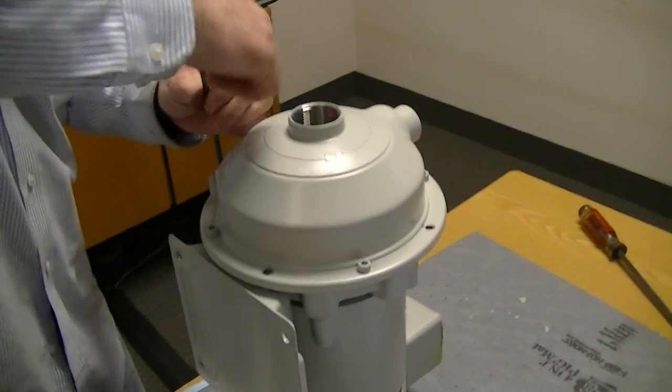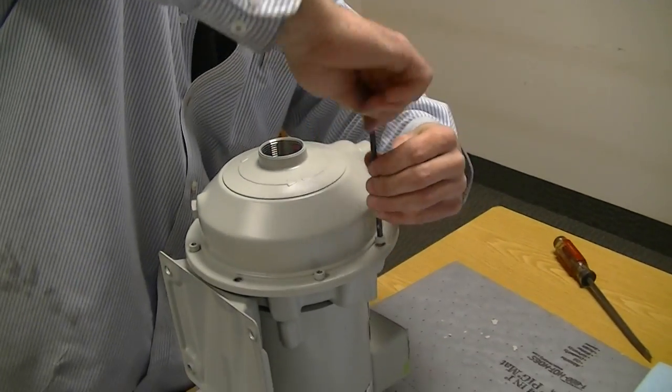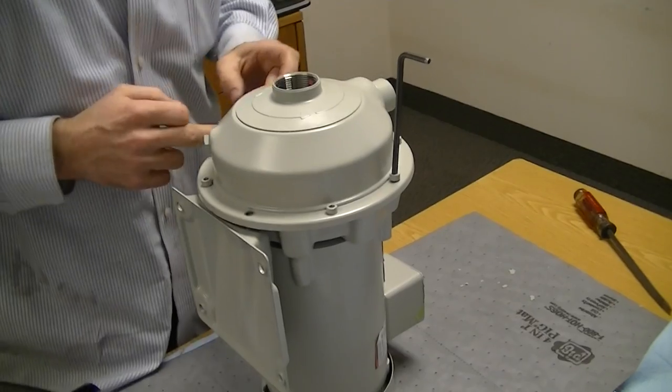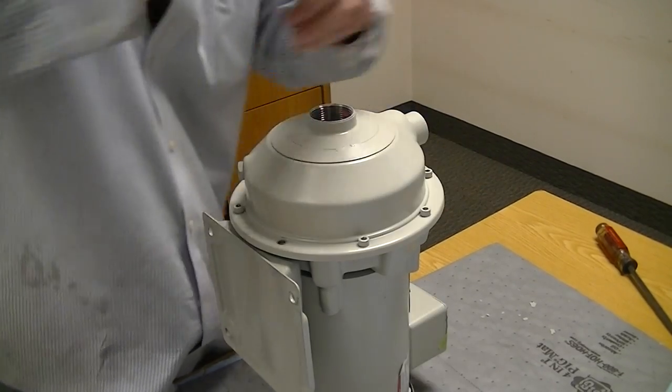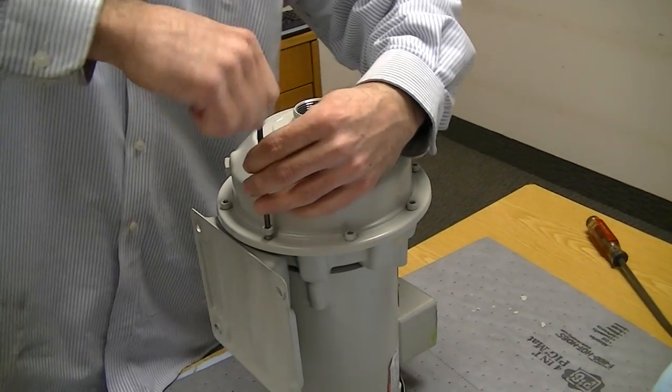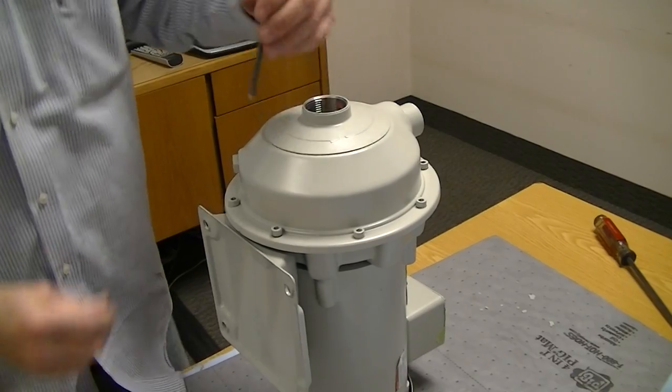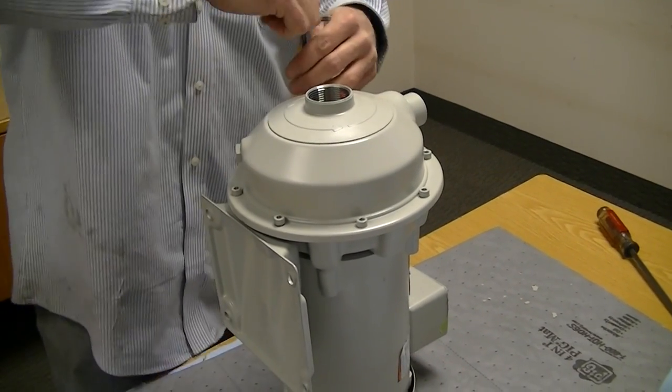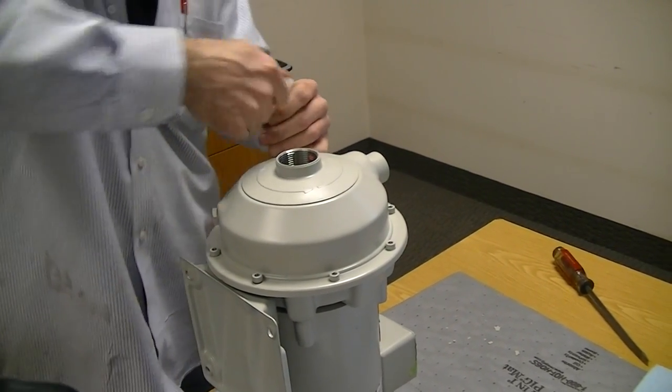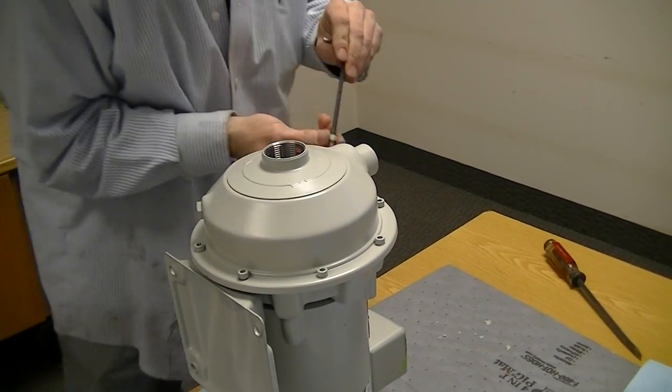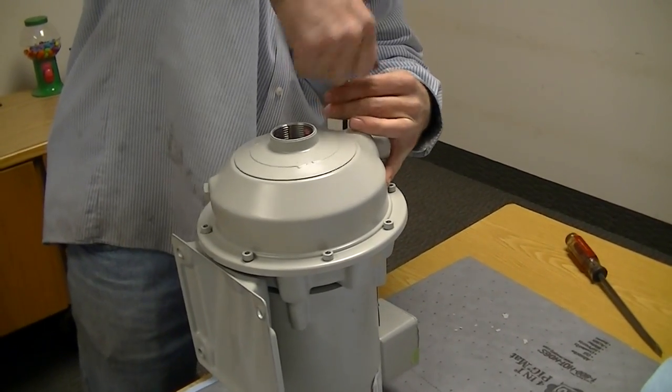It doesn't come off when you're changing a shaft seal. When you build a brand new pump, you'd have to put the O-ring on there. It's a large O-ring that goes around here on the outside. That's the O-ring that we're talking about. It's not something that is usually... there's nothing wrong with those. You don't need a new one when you replace the shaft seal. You can reuse the original O-ring. Unless you see something wrong with it or it's broken or something, you shouldn't have any reason why you couldn't use it.